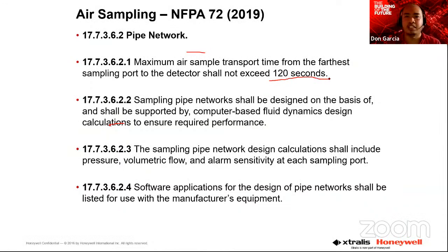This 120 seconds is the standard detection transport time of an aspirating detector. So it means that if you run a pipe and put multiple holes, at the farthest hole you placed, when you spray or test smoke there, the VESDA detector must receive it in 120 seconds or less. If it goes beyond that, your design failed. So you have to revise your design to meet your requirements.